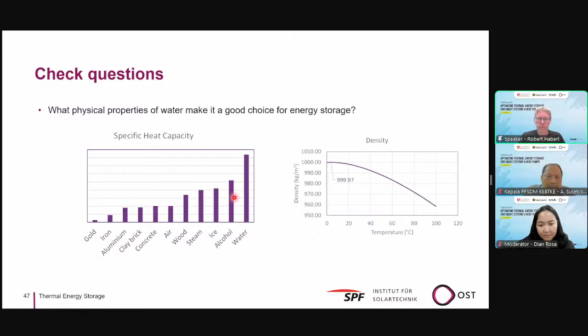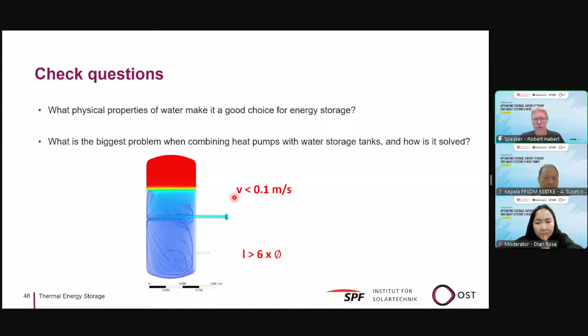The second question was, what is the biggest problem when combining heat pumps with a water storage tank, and how is it solved? The biggest problem is the flow rate of heat pumps. Heat pumps work with small delta T and high flow rates, and the way to overcome that is to have a speed below 0.1 meter per second and a calming section inside the storage tank for charging it.